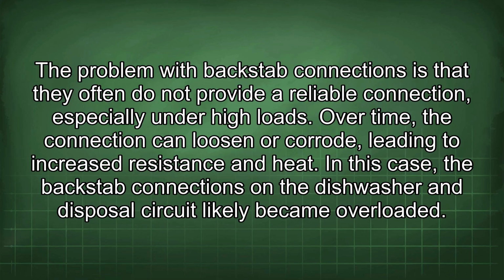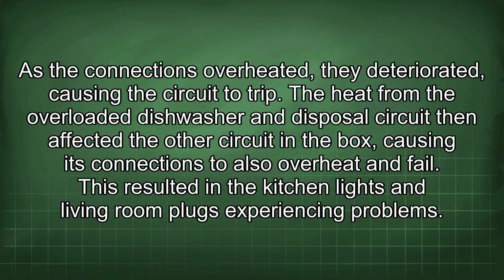In this case, the backstab connections on the dishwasher and disposal circuit likely became overloaded. As the connections overheated, they deteriorated, causing the circuit to trip. The heat from the overloaded dishwasher and disposal circuit then affected the other circuit in the box, causing its connections to also overheat and fail. This resulted in the kitchen lights and living room plugs experiencing problems.